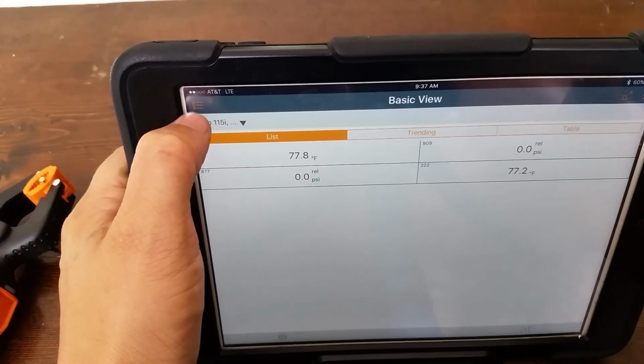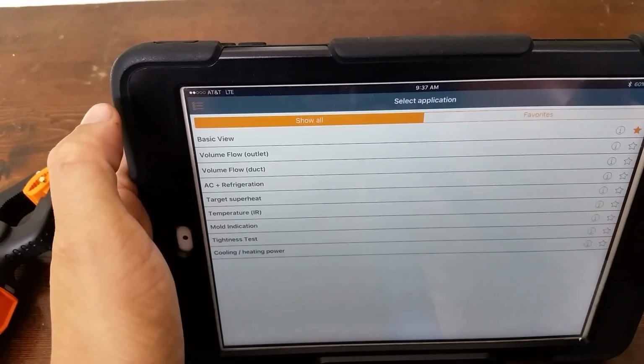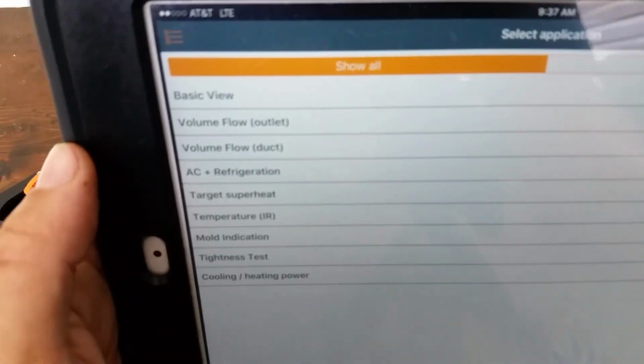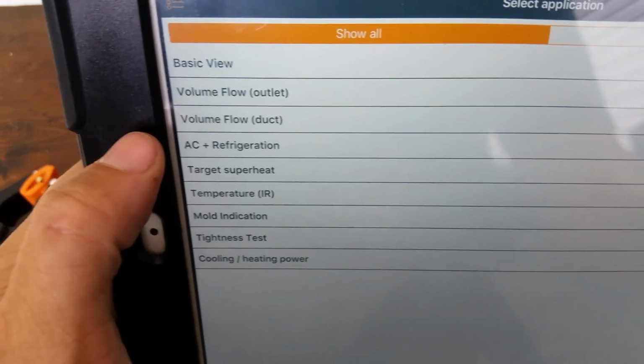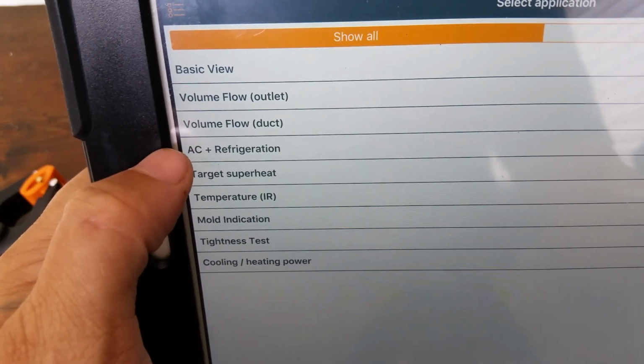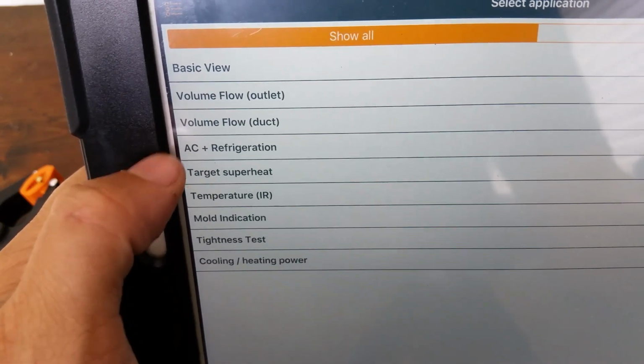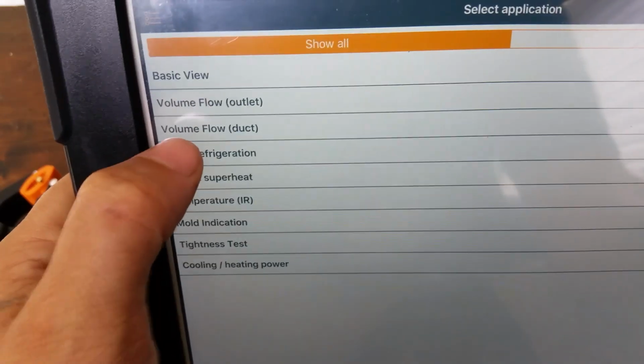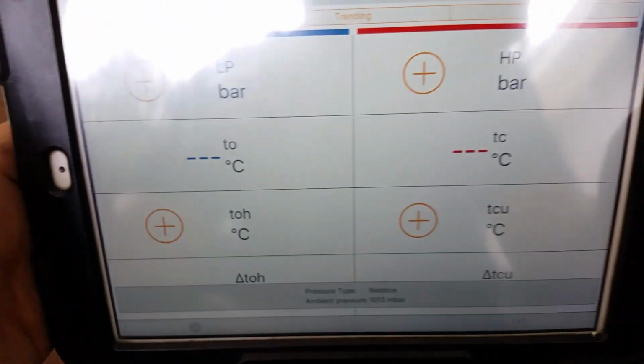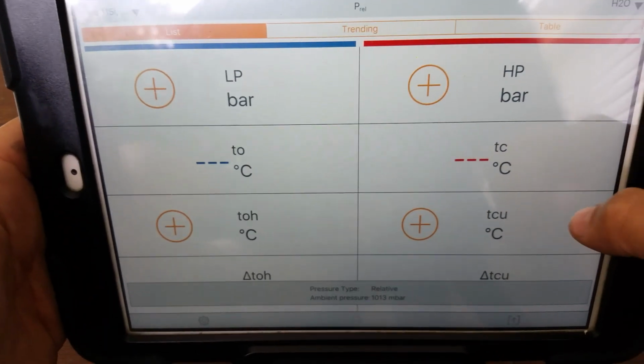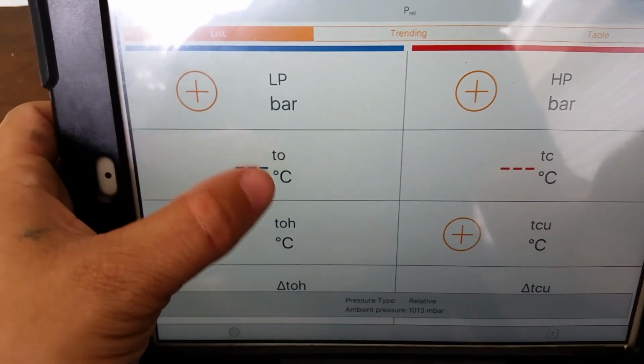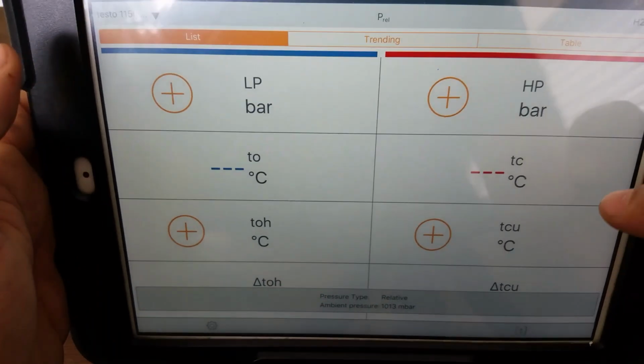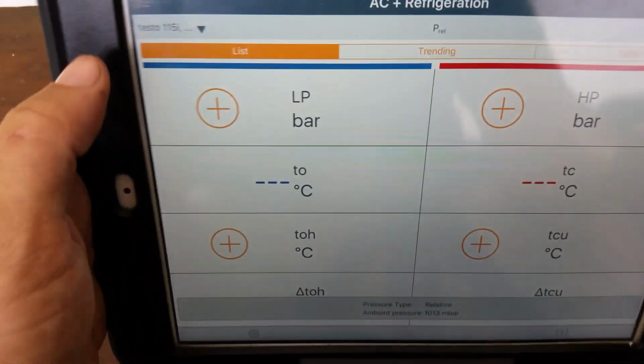If you click this drop-down bar up here, it'll come back to the main screen. Usually when I'm checking the refrigerant charge, I'm typically using either the AC plus refrigeration mode or the target superheat. AC refrigeration mode is going to give you this screen. Again, since I haven't opened this part of the app, I'd need to go in and change from Celsius to Fahrenheit, or whichever measurements you prefer.